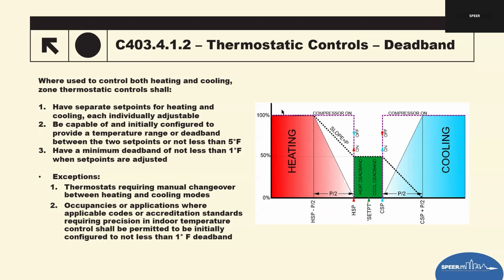Second, have required temperature range and deadband. So the thermostat must be capable of maintaining a minimum deadband of at least 5 degrees between heating and cooling set points. This prevents rapid switching from cooling to heating, something that basically wastes a significant amount of energy, especially during spring and fall and the shoulder seasons. This is also how the thermostat should be initially configured at installation. We're going to look at commissioning some other time, probably in next year's presentation.